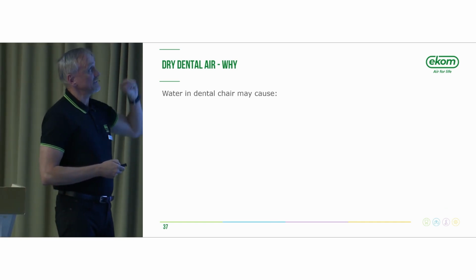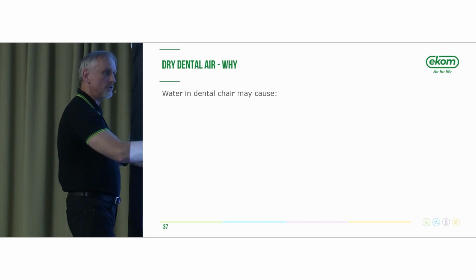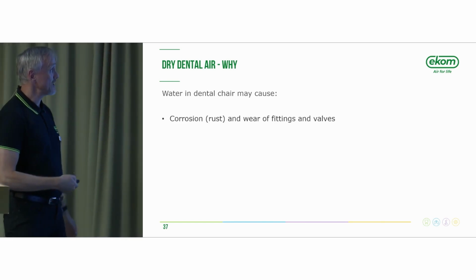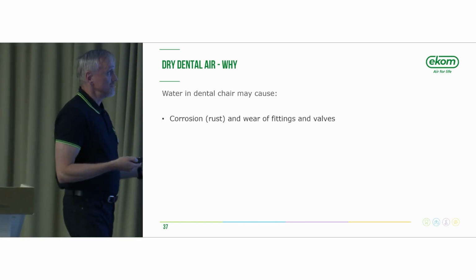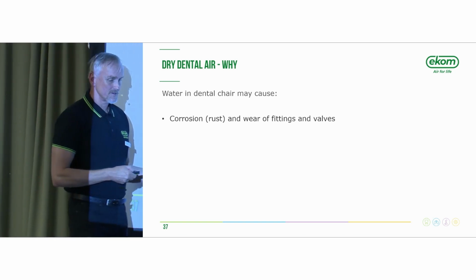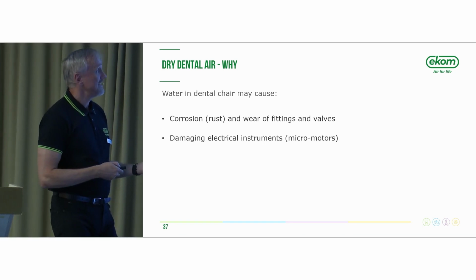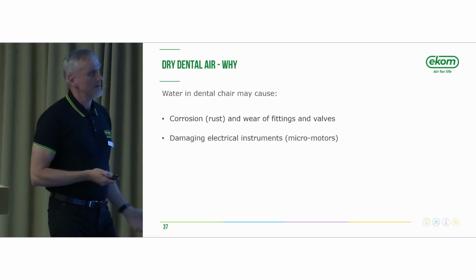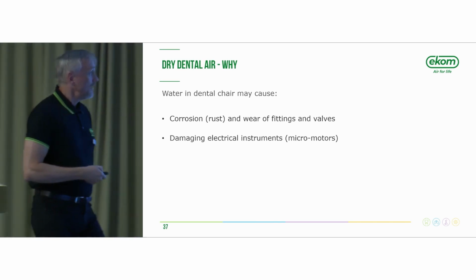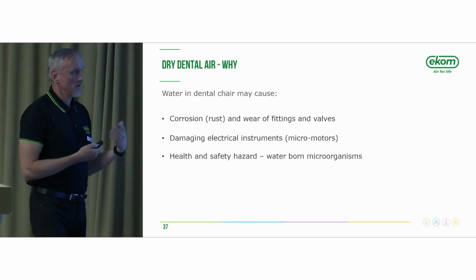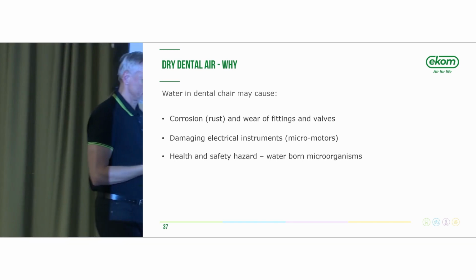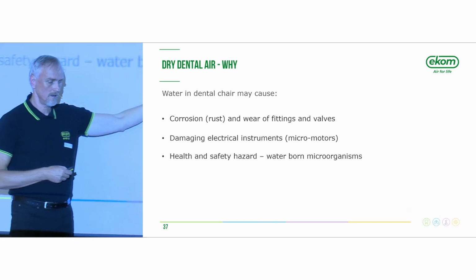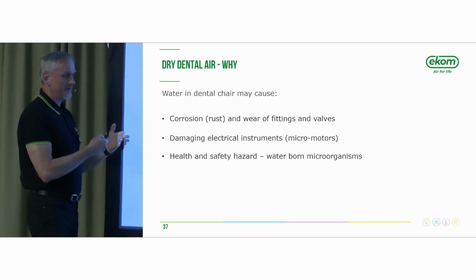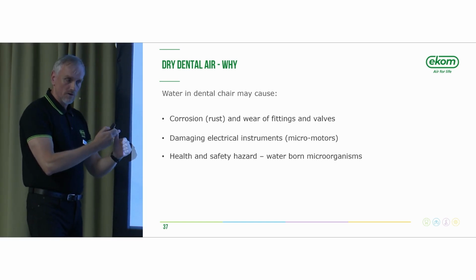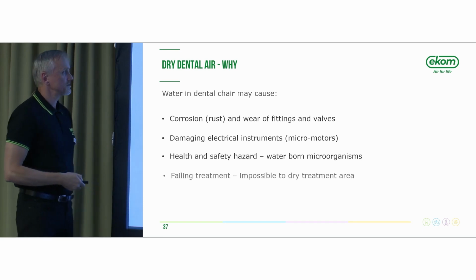And water in the dental chair, if it continues through the system to the chair, what may it cause? Corrosion and wear of the fittings and valves in the dental units, damaging electrical instruments and micromotors, a health and safety hazard, and waterborne microorganisms. This is a very important question - biological compatibility and all this stuff. High temperature plus water is a good ground for growing bacteria.